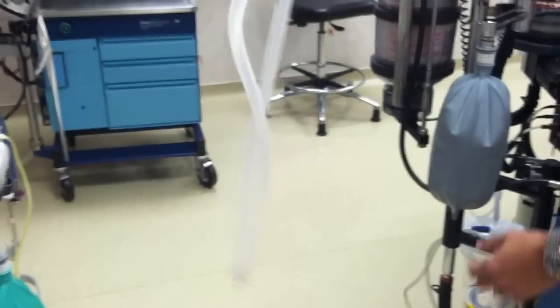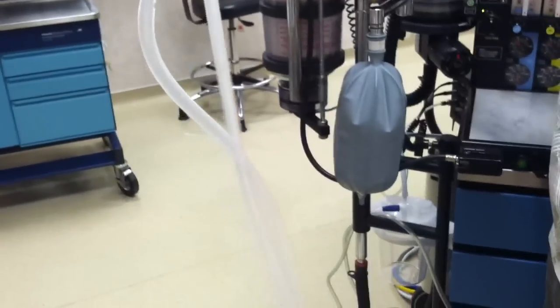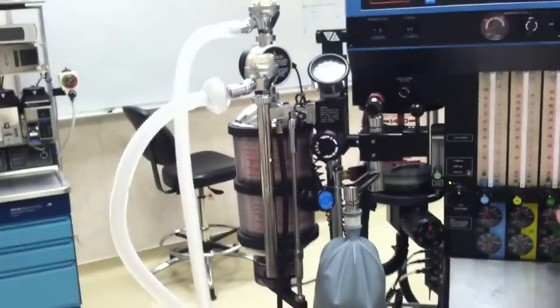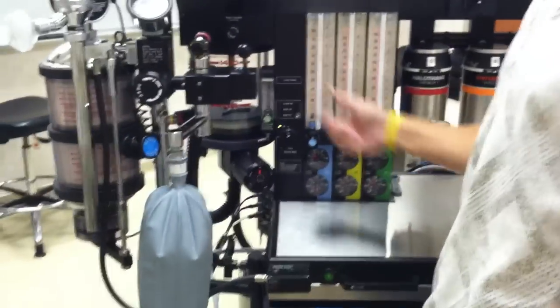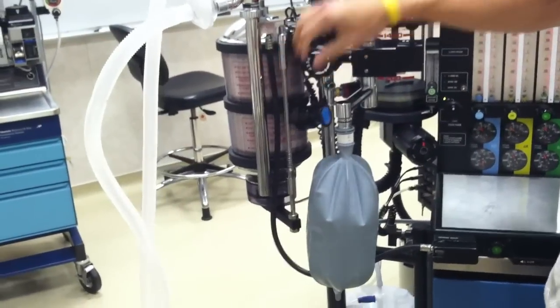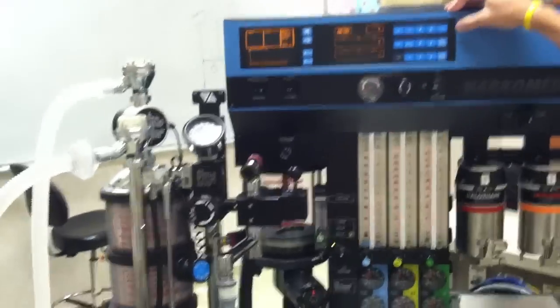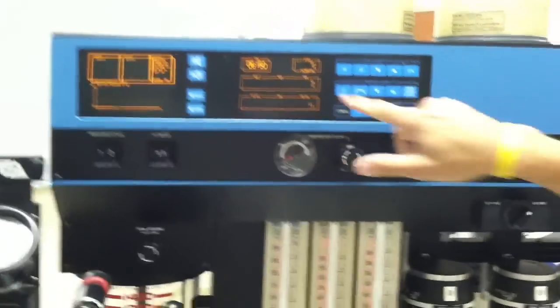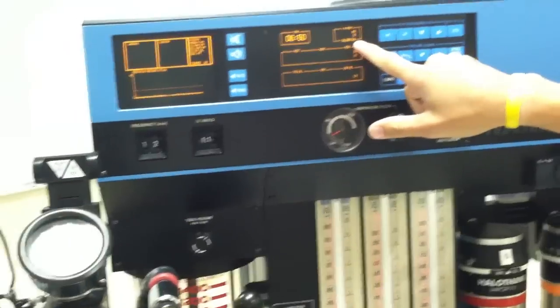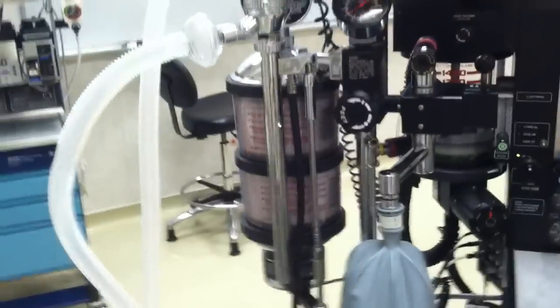Now we're going to go ahead and check our breathing circuit. No, I'm sorry. Now we're going to go and check our O2 calibration. And I remember that by the last thing I touch is the oxygen, so now I need to check the O2 calibration. On this machine, you just open it up to air, push O2 cal, and it says calibrating. For this purpose, we're not going to wait for it to calibrate, we're going to stick it back on.